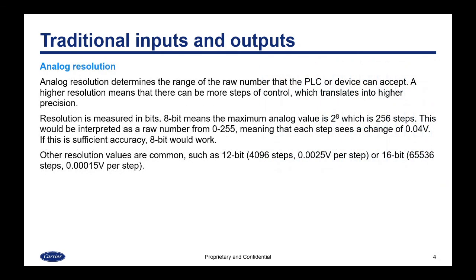An issue with analog is resolution. Analog resolution determines the range of the raw number that the PLC or device can accept. A higher resolution means there can be more steps of control, which translates into higher precision. Resolution is measured in bits. 8-bit means the maximum analog value is 2 to the power of 8, which is 256 steps, interpreted as a raw number from 0 to 255, meaning each step can see a change of 0.04 volts. Other resolution values are common, such as 12-bit with 4,096 steps or 0.0025 volts per step, or 16-bit with 65,536 steps and even finer resolution of 0.00015 volts per step.